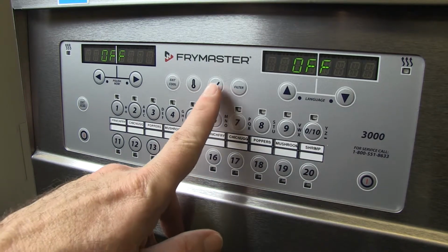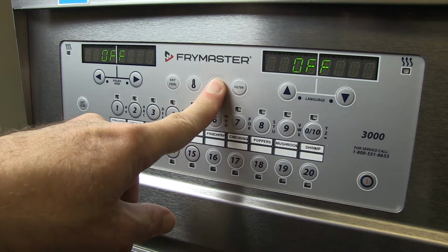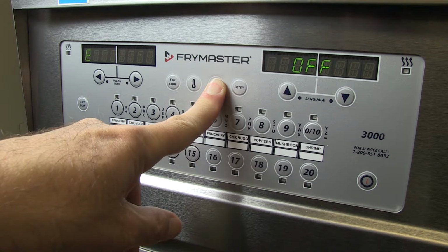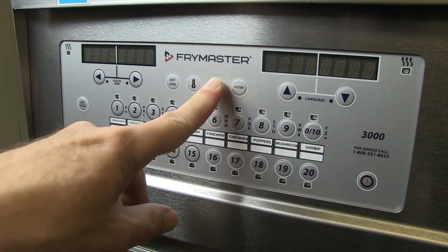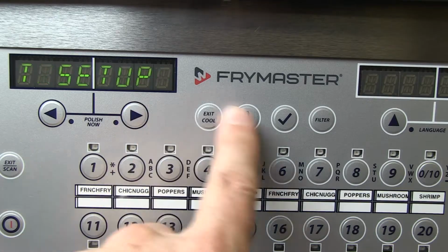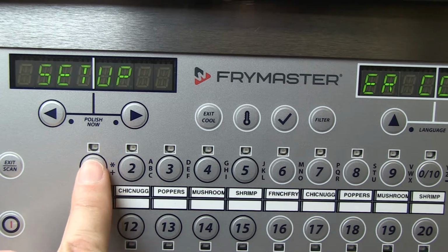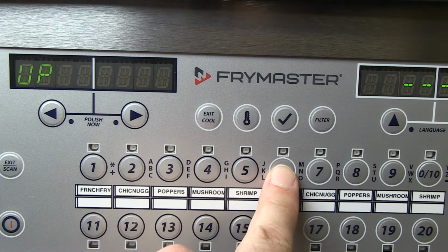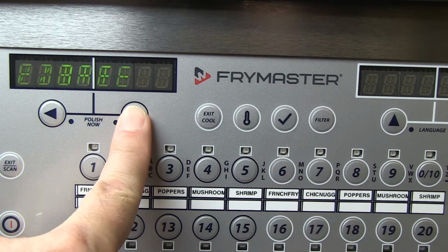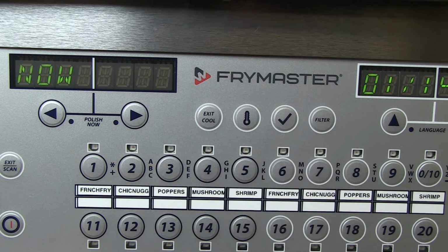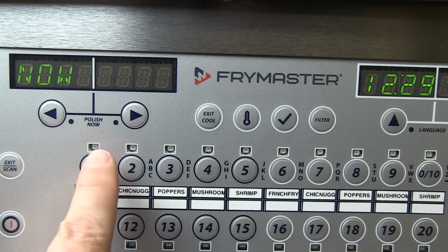Error logs in the 3000 series controller take a few more steps to retrieve. Press and hold the check mark. The screen changes to Info mode and then Main. Scroll on the left side until the VAT setup is displayed. Press the check mark. Enter 1656 at the code entry display. Scroll to E-log. Press the check mark. Scroll the recorded error codes with the arrow keys.